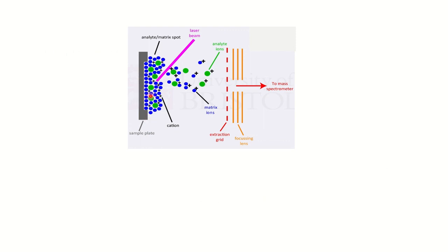So you have a sample plate in which you have matrix where the analyte is dissolved or dispersed. Once the laser beam, the high intensity photon, is bombarded on the analyte, the analyte is ionized with the high intensity beam. It is now ionized in the form of cations and will travel towards the mass analyzer and be analyzed with respect to m by z ratio.